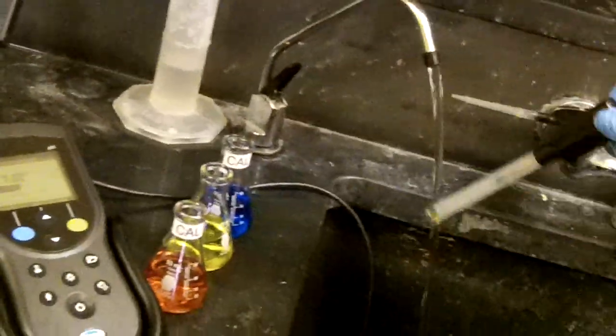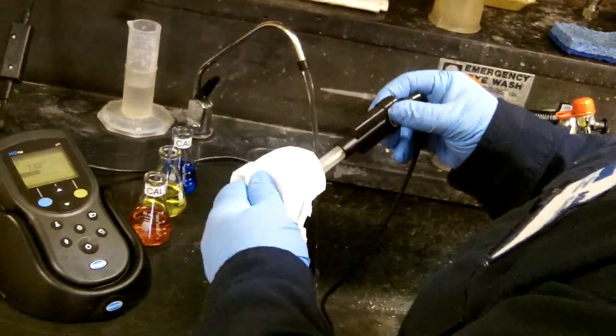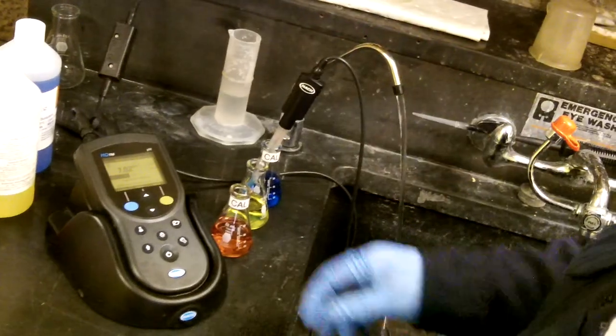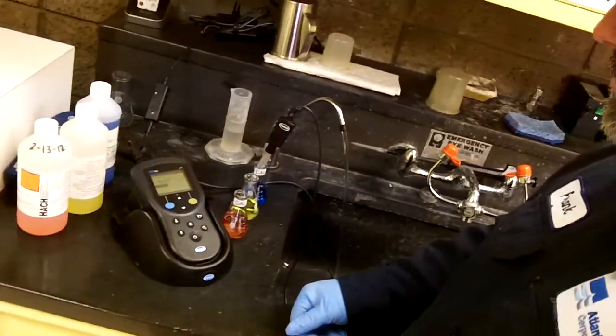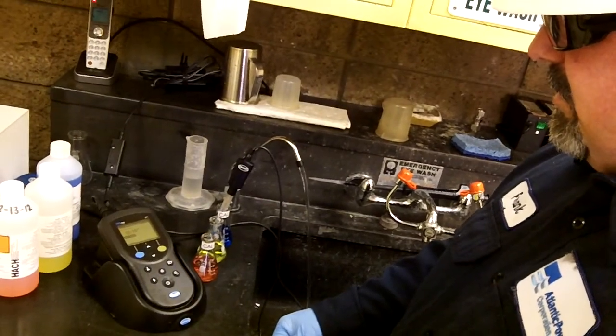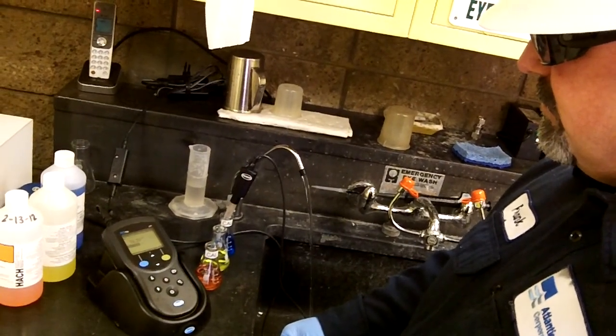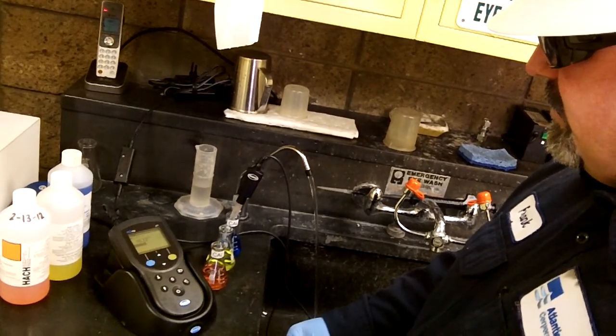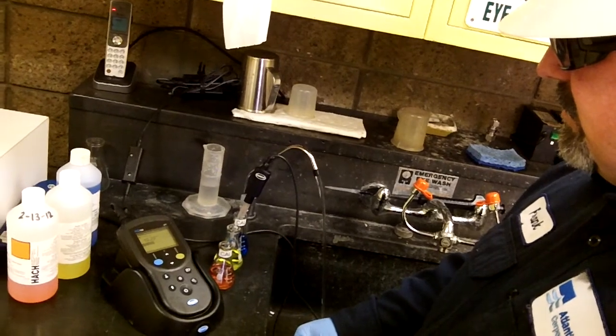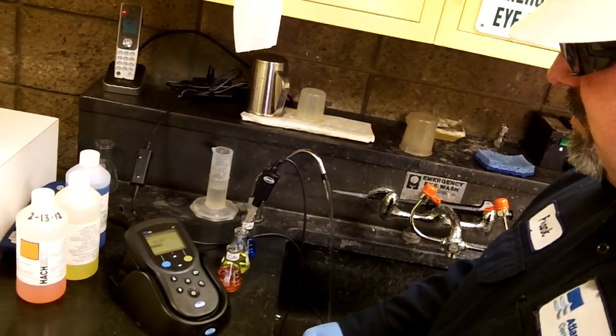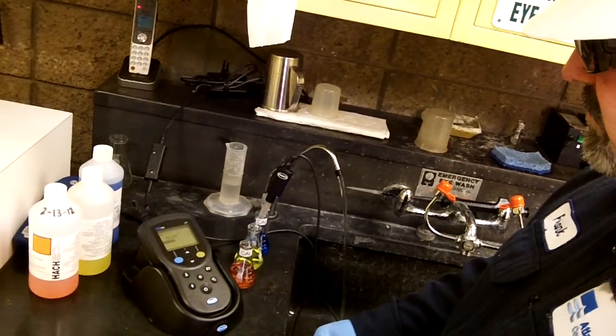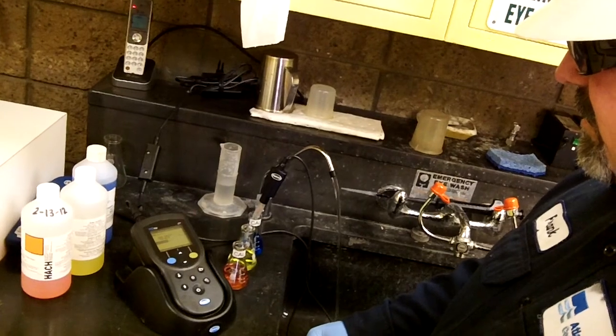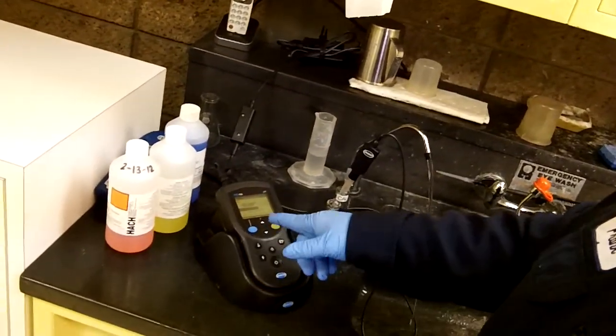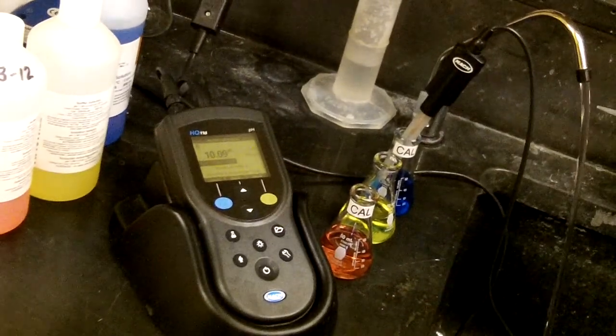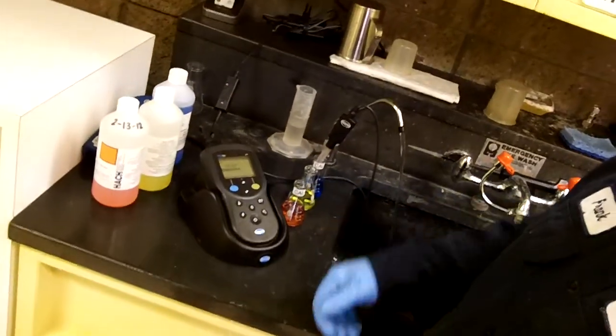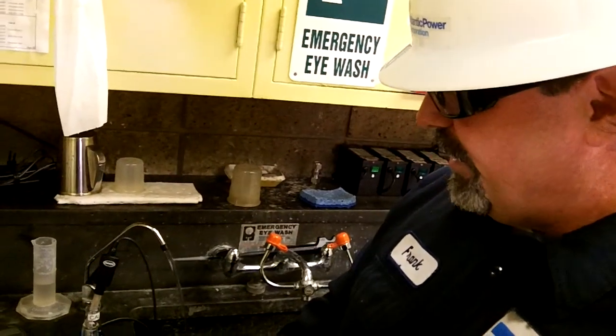So now we're going to take this out of here. We're going to rinse it with DI water. Wipe it dry, put it in the 10, hit read, and it's going to start a stabilization. And that came out at 10.09. So that's okay. Like I said, if it was at 10.5, then we would worry about it. But we're at 10.09, so we're good.